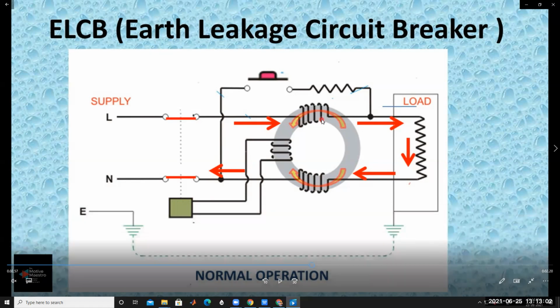Understood? For example, flux phi 1 is 1 Weber. Here phi 2 is also 1 Weber. So the resultant flux is 1 minus 1, which is zero, because they are in opposite directions. Understood? So that's why there is no resultant flux induced in this sensing coil, and the tripping coil is not working. The sensing coil is not sensing any flux. Because the resultant flux is zero, it is not sensed, and the tripping coil is not working. That means it is in the safe region.